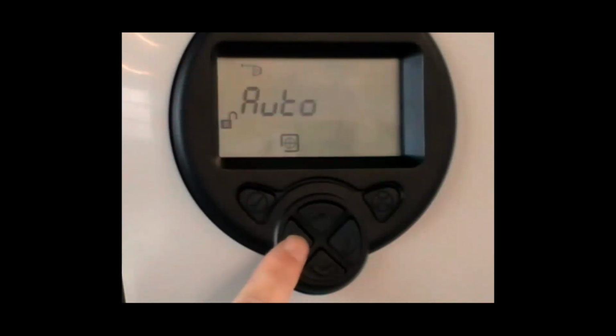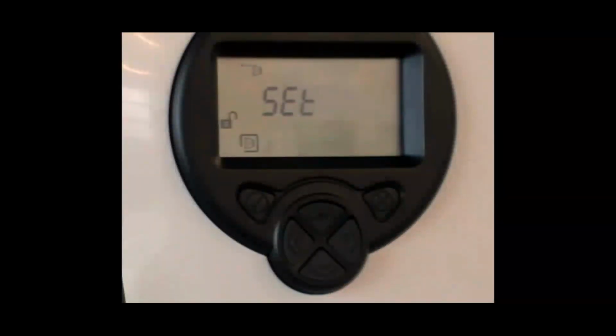In the alignment menu, there are two options: Hand and Auto. Hand is only used by advanced users in troubleshooting, so select Auto from the alignment menu and press Tick. The auto alignment will take approximately 3 minutes, during which detector signal strength can be viewed on the display. This procedure ensures the best alignment and detector power for the installation. If the system detects a problem, an error code is displayed on the LCD. Refer to the user guide for error codes. When finished, Set will be displayed.